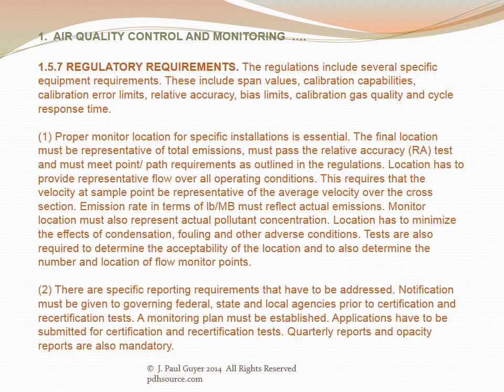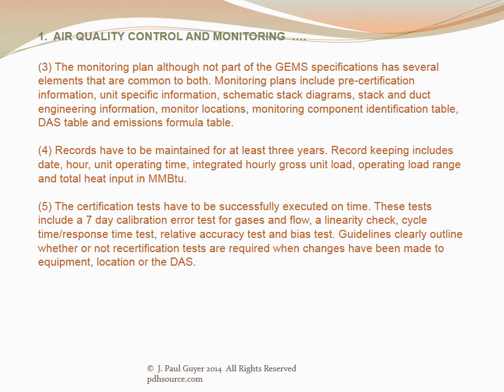There are specific reporting requirements that must be addressed. Notification must be given to governing federal, state, and local agencies prior to certification and recertification tests. A monitoring plan must be established. Applications have to be submitted for certification and recertification tests. Quarterly reports and opacity reports are also mandatory. The monitoring plan, although not part of the CEMS specifications, has several elements common to both.